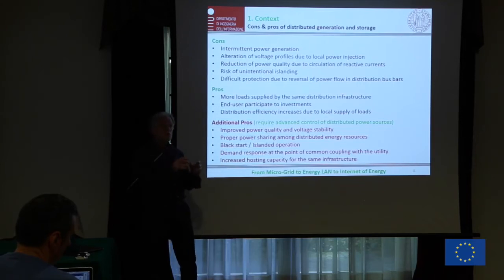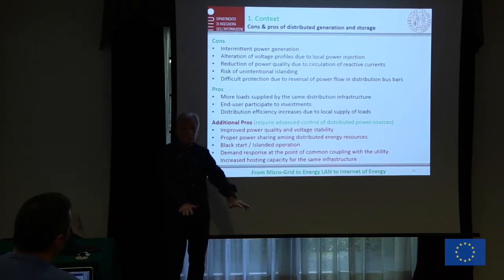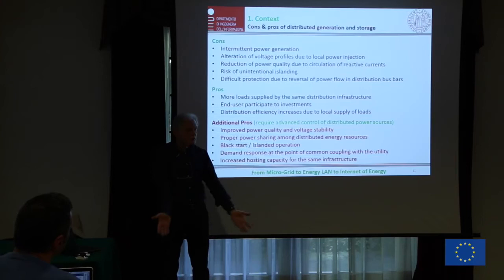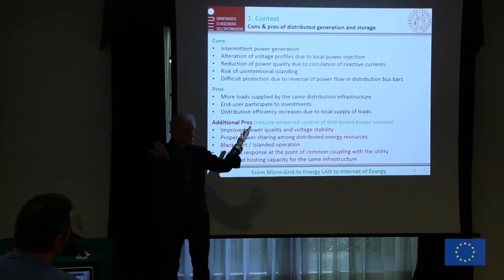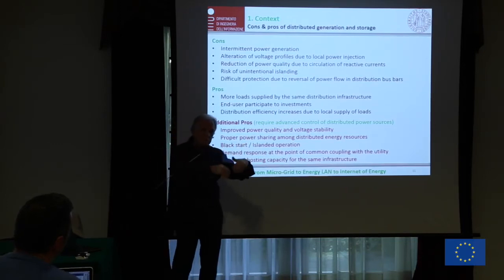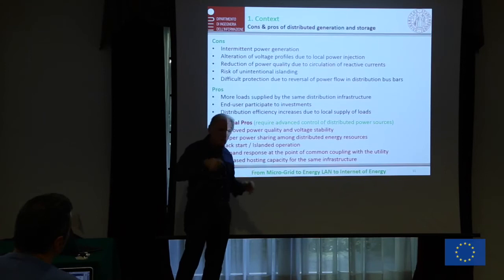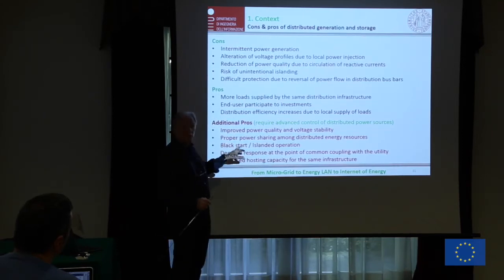Black start is the situation where the grid is down and you have to start it from zero. This is very complex normally, because with synchronous generators you have to bring them up quickly and synchronize them. With the help of electronics and distributed power sources, it's much easier to help the grid come up.